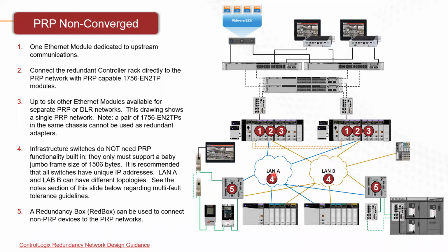But what's interesting here is we can really do some mixing and matching. Like for instance, we're coming to our red box switch here, and then from the red box switch, we can actually create a ring of devices through our ETAPs and stuff. Through this red box switch, we can go directly to our IO chassis, these two being ControlLogix 1756 IO chassis, and then we can also bring in our MCC through another red box switch, and then also maybe have a ring of various MCCs out here in our powerhouse through that as well.